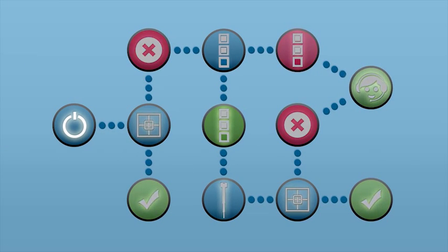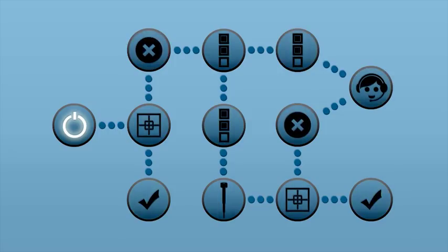Let's review the steps for basic troubleshooting on the MagPix instrument. If you are experiencing issues with your instrument: 1. Run a calibration and verification cycle. If this doesn't work, 2. Run a self-test. If any errors are reported, call technical support. 3. Remove the probe. 4. Clean it. 5. Then replace it and make a height adjustment. 6. Run a system clean. 7. Then run another calibration and verification cycle to see if the problem is resolved.